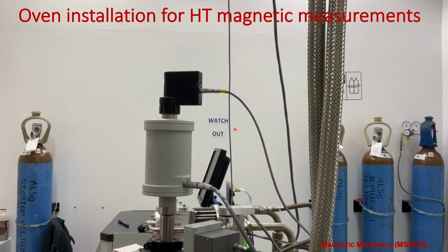That's done. For high temperature measurement, we need a high vacuum of 10 raised to power minus 7 torr. If for some reason the system cannot generate that high vacuum, then we cannot measure the magnetic property at high temperature.